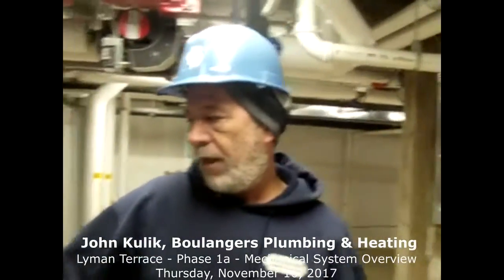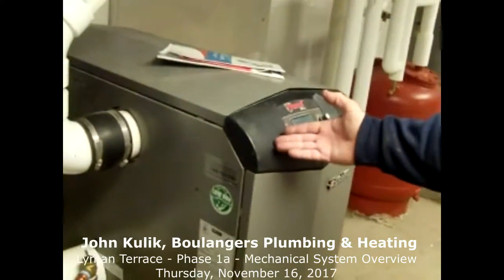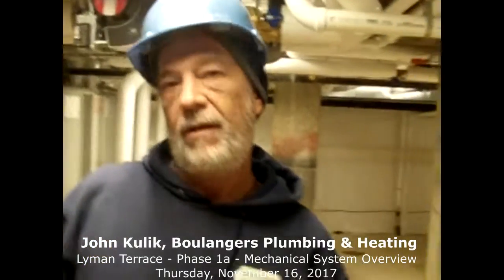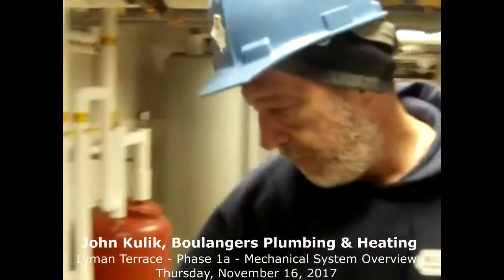There's a redundant boiler also that shares the wealth. It's a cascade system, meaning that there's a lead boiler and a lag boiler. If either of the boilers would shut down, the other does take over. And that is a function that's built into the system as a fail-safe. So the system can be satisfied with just one boiler running? Correct. Wow. So it's 100% redundancy? Yes. Okay. And these are condenser boilers, which we'll get into in a minute. Yep, but they do make condensate.